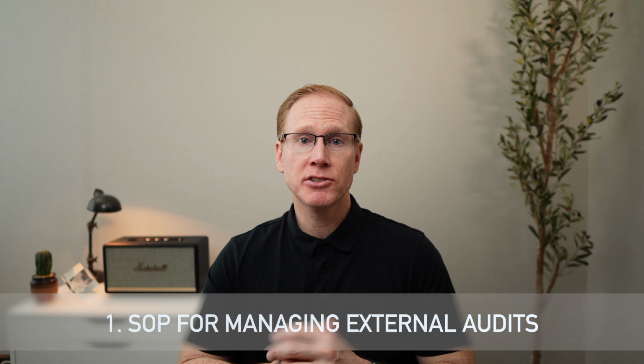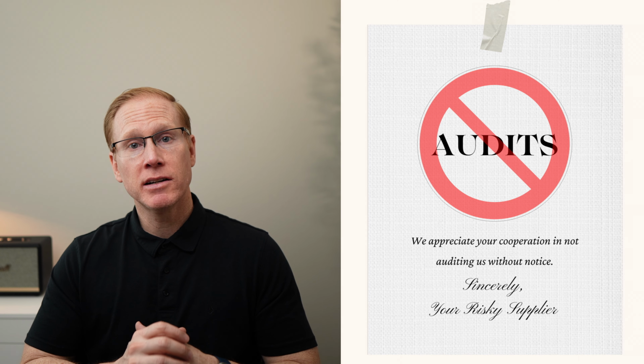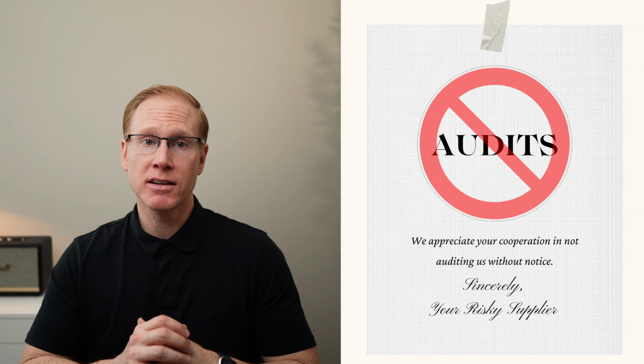If sufficient control of suppliers cannot be demonstrated, then you need to make sure your suppliers are well prepared for both announced and unannounced on-site audits. This is where step 3 comes in, which is to prepare your suppliers for notified body audits. First, start by making sure the supplier has an SOP established with procedures for managing external audits and the resources at the ready to support both announced and unannounced audits. If the supplier does not have such a procedure, help them establish one.